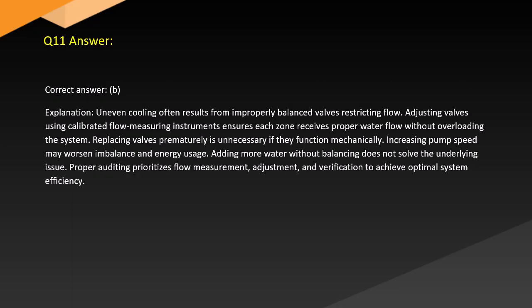Answer. Correct answer: B. Explanation. Uneven cooling often results from improperly balanced valves restricting flow. Adjusting valves using calibrated flow measuring instruments ensures each zone receives proper water flow without overloading the system. Replacing valves prematurely is unnecessary if they function mechanically. Increasing pump speed may worsen imbalance and energy usage. Adding more water without balancing does not solve the underlying issue. Proper auditing prioritizes flow measurement, adjustment, and verification to achieve optimal system efficiency.